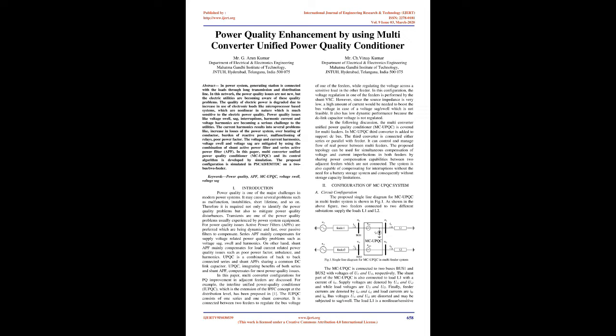compensate. Series APF mainly compensates for supply voltage related power quality problems such as voltage sag, swell and harmonics. On the other hand, shunt APF mainly compensates for load current related power quality issues such as poor power factor, unbalance, and harmonics. UPQC is a combination of back-to-back connected series and shunt APFs sharing a common DC link capacitor. UPQC, integrating benefits of both series and shunt APF, compensates for most power quality issues.